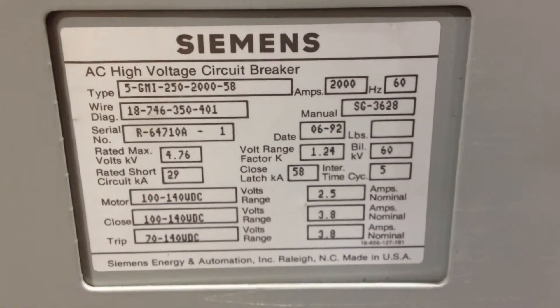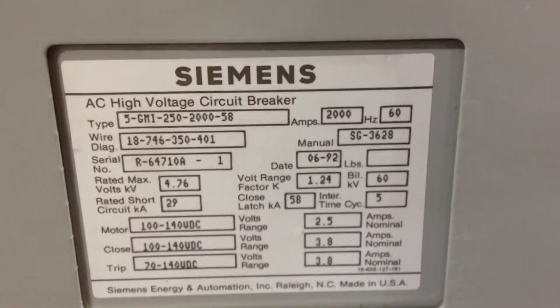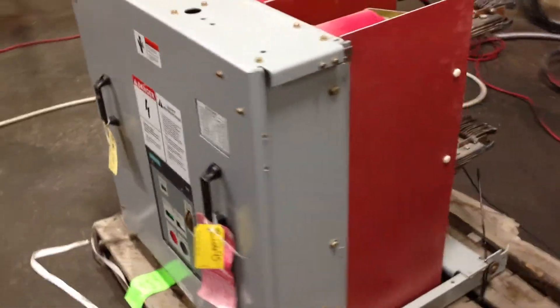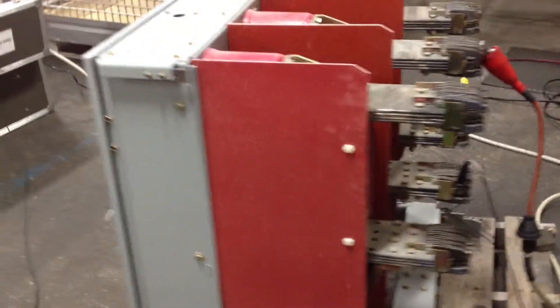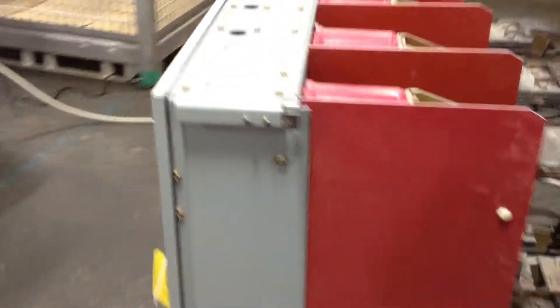Hey guys, we're listening to some good rock and roll right now. We've got a Siemens GMI 250 2000 amp and Aaron is currently hypotting the bottles on these at 11.4 kV. We just got these in, they're stock.